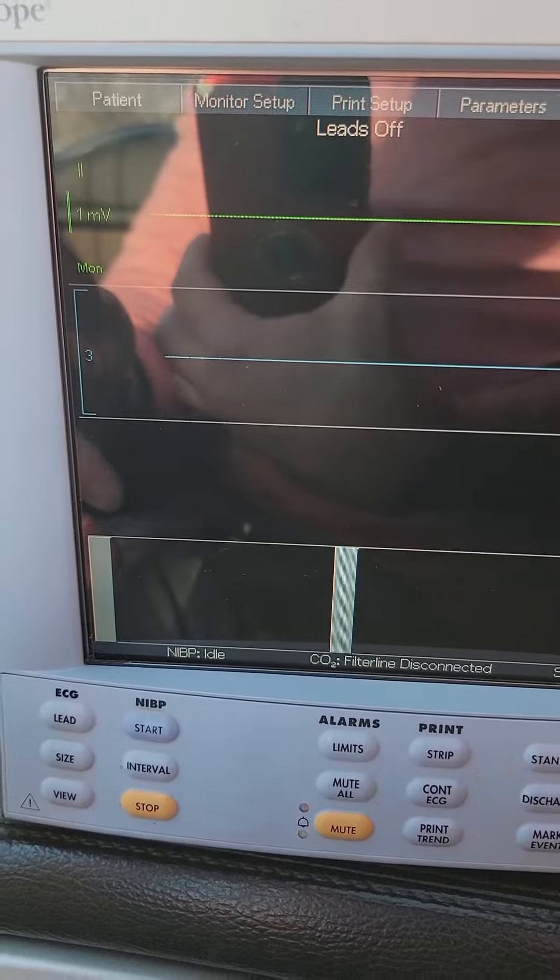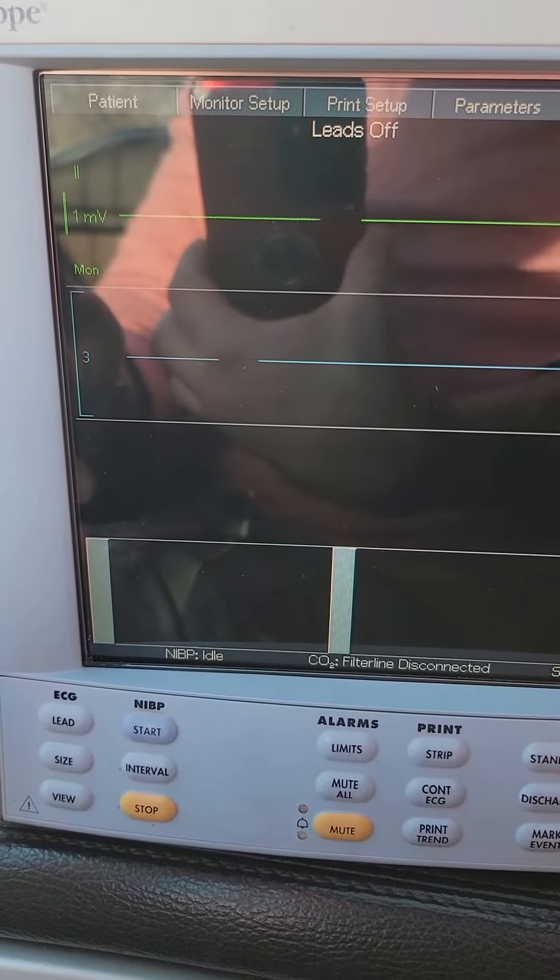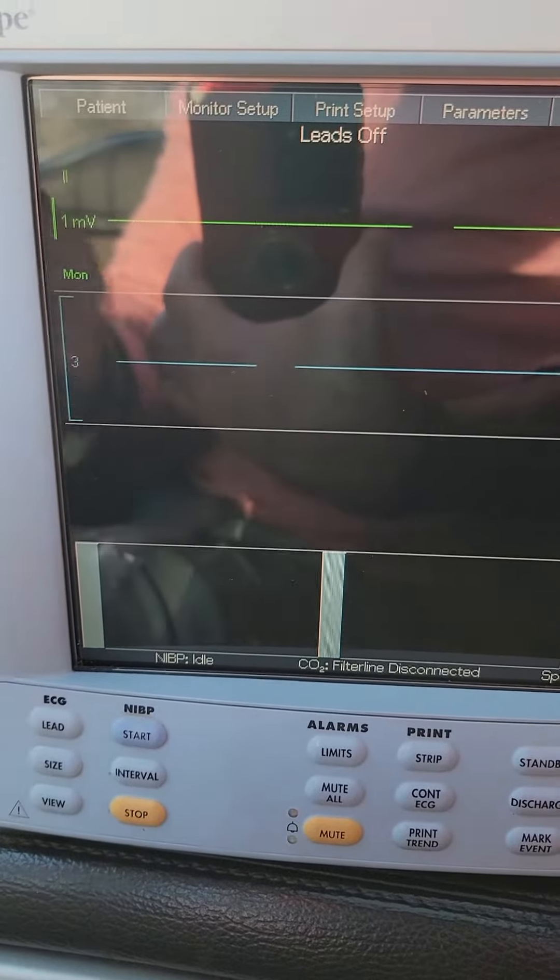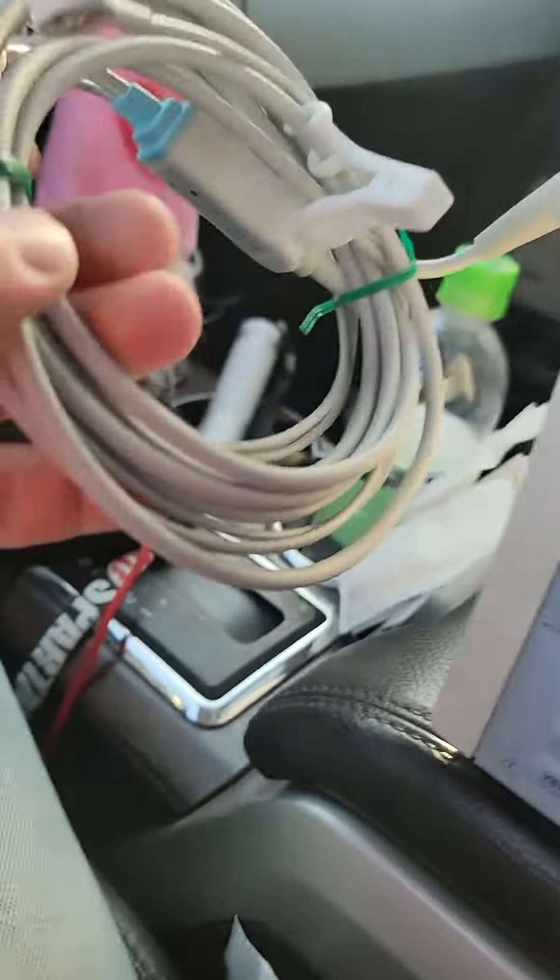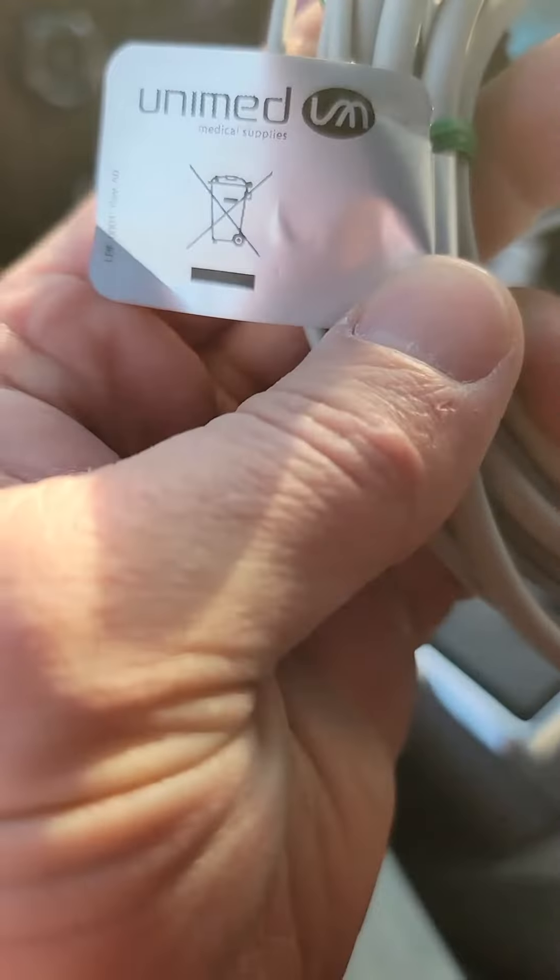They detect between 3-lead and 5-lead, which used to be a great thing, but that only works if you buy the name brand EKG leads that go with this manufacturer.